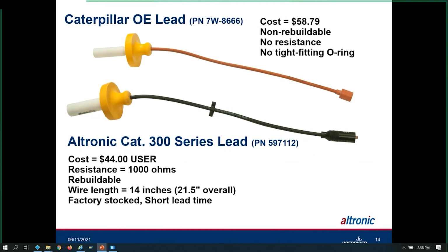That secondary wire is roughly $1 a foot, and you can rebuild that. It might be 1.5 feet long. Well, it's 14 inches wire length, so it costs you $1.50 to put new wire in there. But the idea is you can rebuild them if you want. My experience with a lot of these people out in the field, when it comes down to a price of $44, they don't mess with it. They throw it away and buy new ones. But you might have a customer that's frugal, so then he has both choices. He can rebuild these things himself.